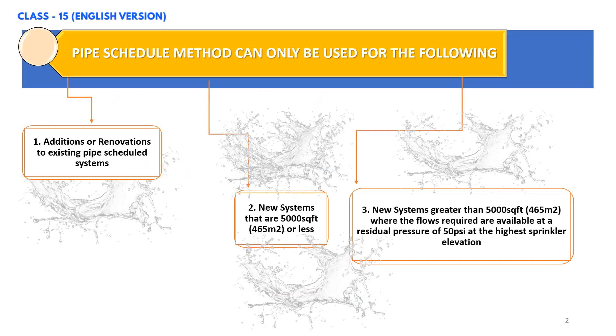As you can see on your screen, the pipe schedule method can only be used for the following three points. Number one: additions or renovations to existing pipe schedule systems. Number two: new systems that are 5,000 square feet (465 square meters) or less. And number three: new systems greater than 5,000 square feet or 465 square meters where the flows required are available at a residual pressure of 50 psi at the highest sprinkler elevation.